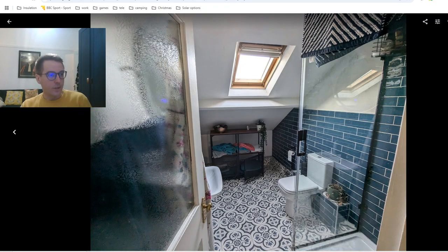One of the things you do is a room by room heat loss. So this is our bathroom. We've got a towel rail behind here. They don't have any heat, but it'd be a little bit difficult for us to take a flow and return and put an extra one in behind the little cupboard we have for towels, etc. And so what you can do is oversize the next door room. So we can oversize some of the other attic rooms. And if you leave the door open, or if you just have the heating on all the time, these things will sort of even out. So that's one thing you can bear in mind on your heat loss survey.